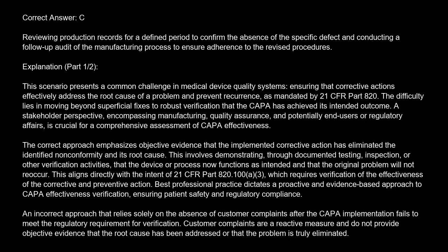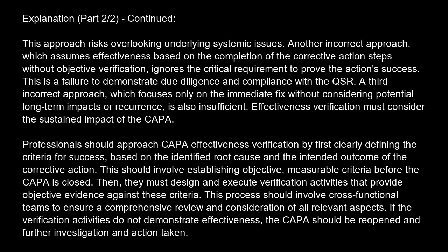An incorrect approach that relies solely on the absence of customer complaints after the CAPA implementation fails to meet the regulatory requirement for verification. Customer complaints are a reactive measure and do not provide objective evidence that the root cause has been addressed or that the problem is truly eliminated. This approach risks overlooking underlying systemic issues.